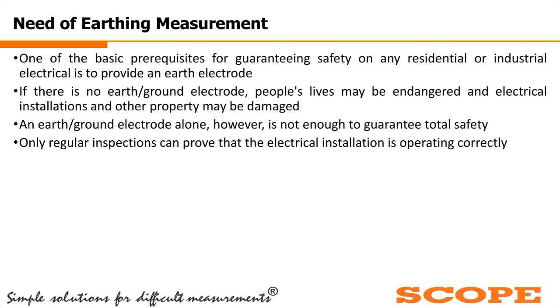Because it is one of the basic prerequisites for ensuring the safety of the operator. If there is any leakage current flowing through any electrical equipment's body, then any user who comes in contact with the equipment may get a severe shock. To avoid this type of electrical accident, it is very important to measure the earthing systems or the earthing resistance periodically. If there is no earthing or grounding electrode, it is very dangerous for any people.